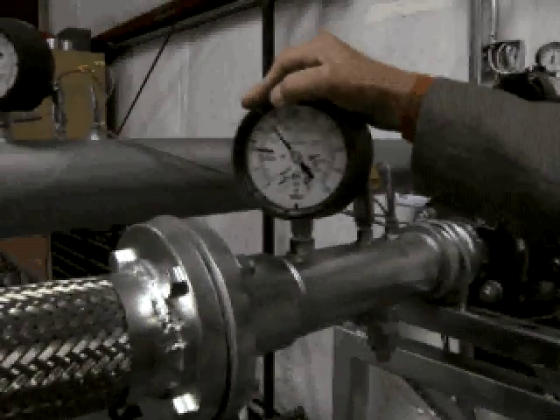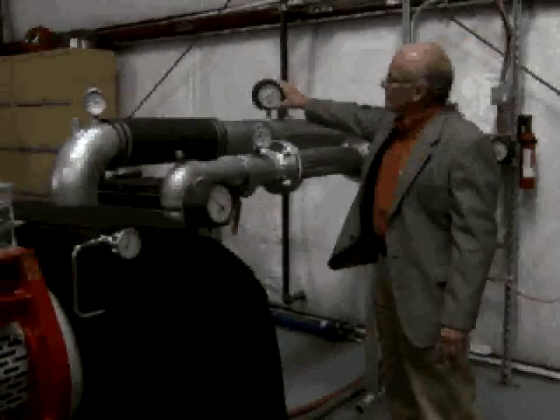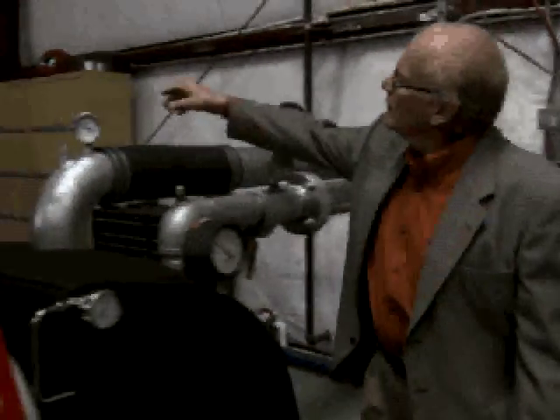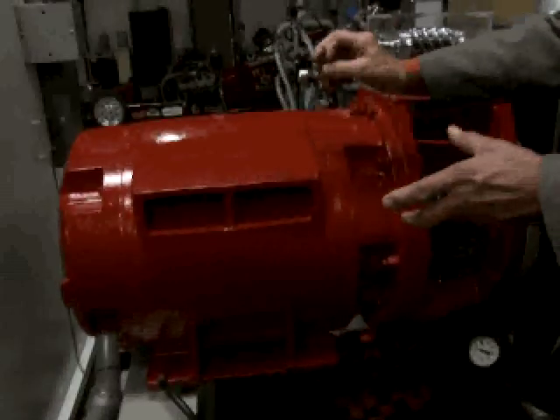Let's go ahead and light this candle. Chris, do you want to give us a hand and start this machine? As you can see, we're generating 63 kilowatts within four seconds. We're running at 70 psi on the inlet side and 180 degrees on the temperature. As we go through the machine it drops to 18 degrees, 17 degrees coming out of the exit, and the pressure is running about two pounds on the other side. So we're going from 70 pounds to two pounds, from 185 to 18 degrees in a microsecond. All that energy is going into the generator to generate clean green energy out of waste.